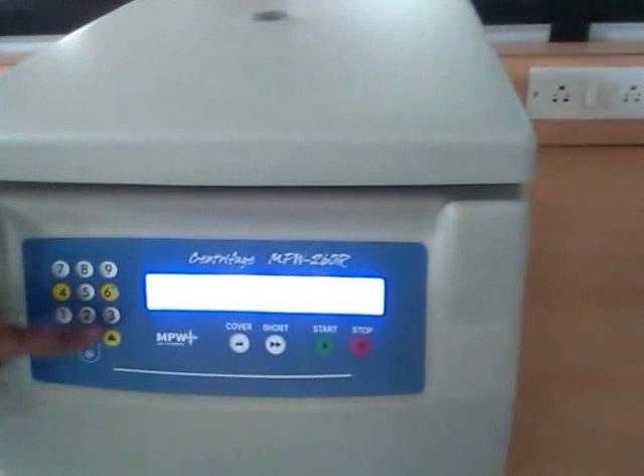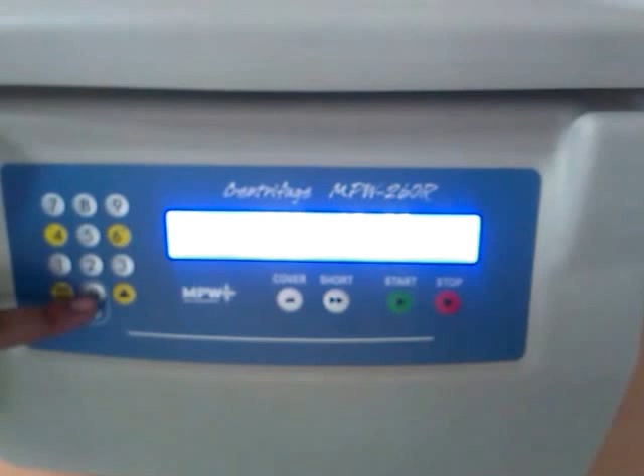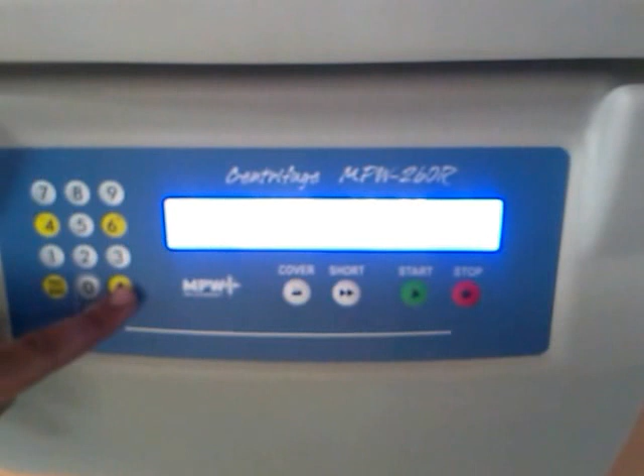Then coming to the main panel, we have a numeric keypad here, which helps in programming all the parameters of the machine. Numeric keys from 0 to 9, and then we have program and the changing key for all the parameters. Then we have a cover switch if you want to open the lid of the machine during the operation or after the operation. This is a very important key for the short spin or the short centrifugation that you want to do. Start button and the stop button.